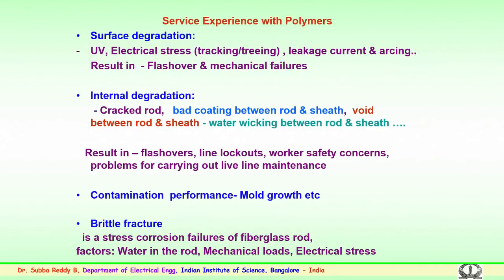So, the bad coating could also cause internal degradation over a period of time, or the voids, small air pockets between the rod and sheath, could again lead to the air pockets getting discharged, charge build-up, and failure because the insulation becomes weak at those junctions, where these small air pockets could break down. Water entering these places could further, in case of microstructure damage to the fiberglass rod, form acid, which could contribute to the failure through internal degradation between the rod and the sheath.